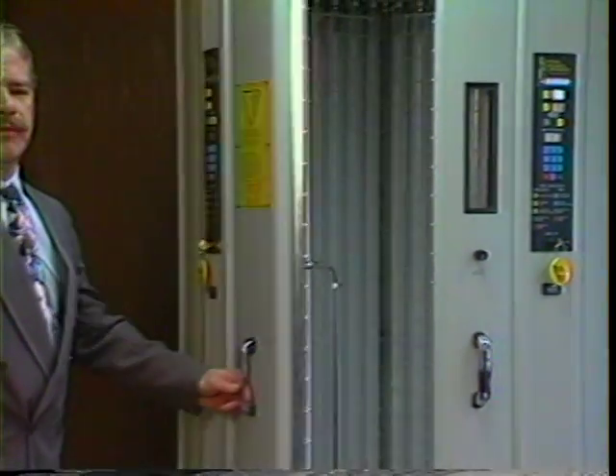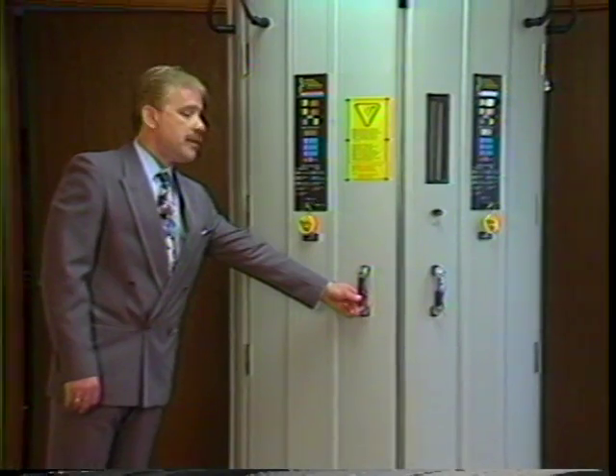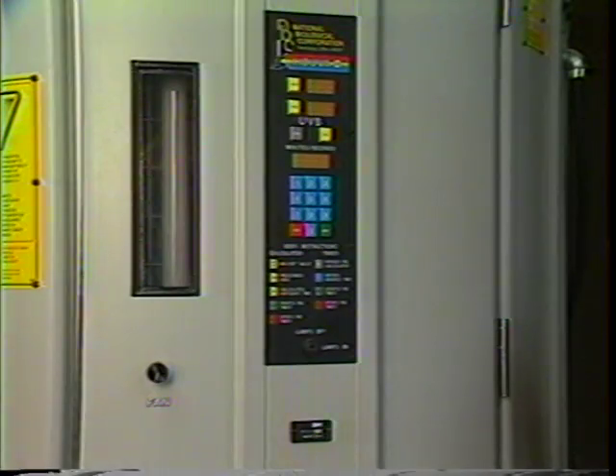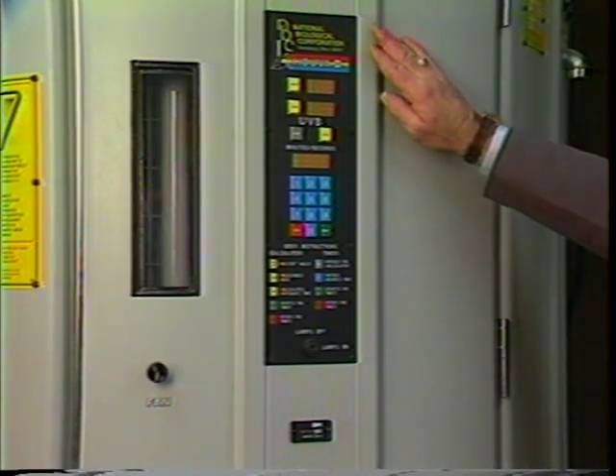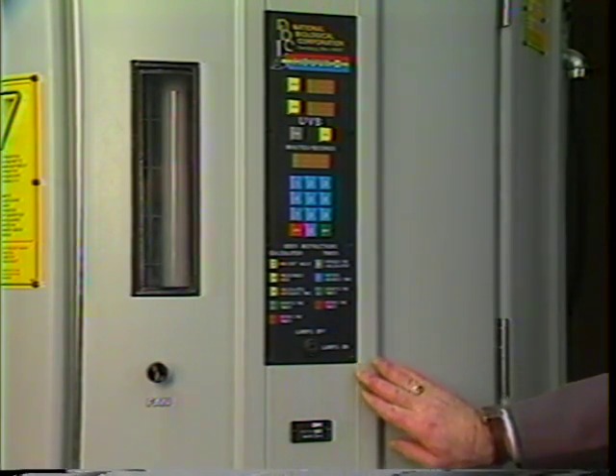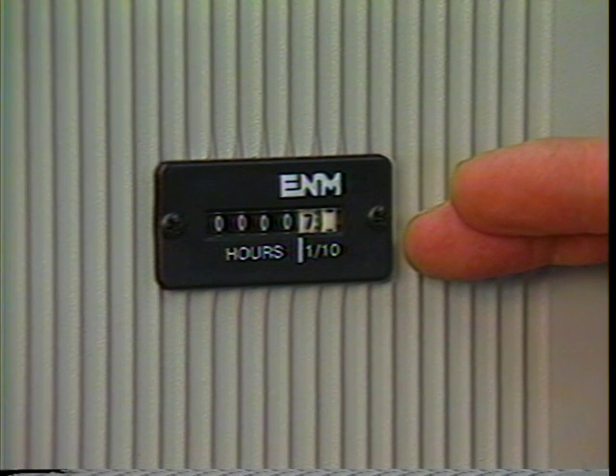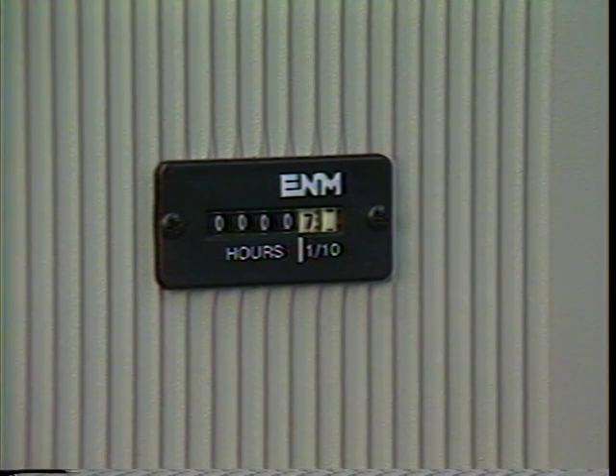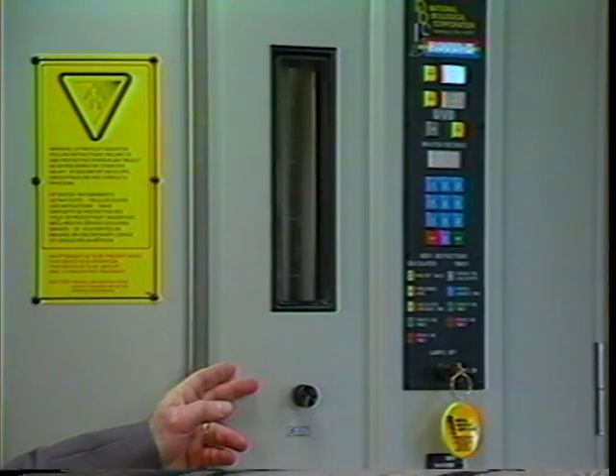Another design and safety feature found in the HOUVA II system is the PhotoSense exposure control. It provides automatic calculation for exact treatment times. This significantly reduces human error. This also utilizes an independent timing system for UVA and UVB therapy requirements. Just below the PhotoSense timers are the cumulative hour meters. These measure useful lamp life. There is a variable speed fan switch with which you can set the perimeter flow ventilation system to any desired airflow. This is a feature found only in the HOUVA II system.